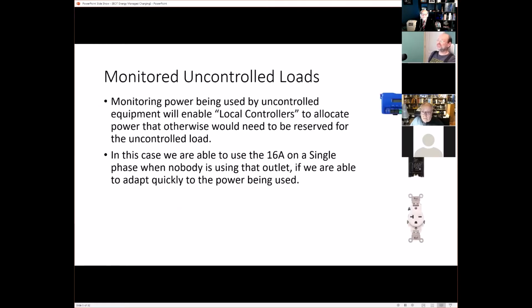The next step is if we add electrical meters onto this system, we can monitor the power that this outlet is using at any time. That will allow us to use the power we would normally have had to reserve for that plug, and now we can use it when no one's using that 110 plug. And when someone does plug in, we have to turn down the EV chargers to make room for that new load.